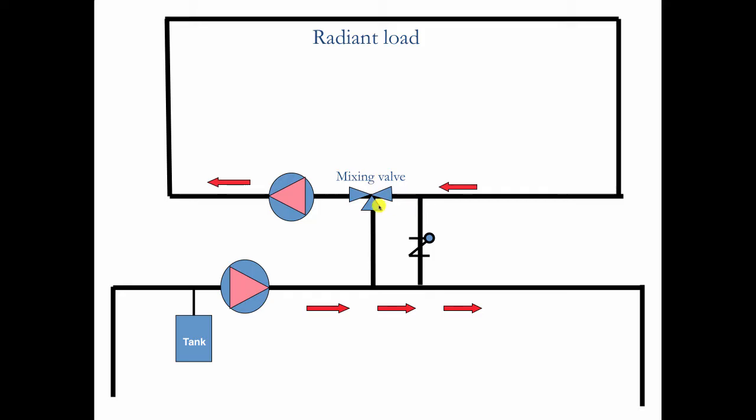Now we've got a three-way mixing valve. This is the hot port, the relatively cold port, and the mixed port over here. And then we've got a flow control valve to stop migrating hot water from entering this flow.